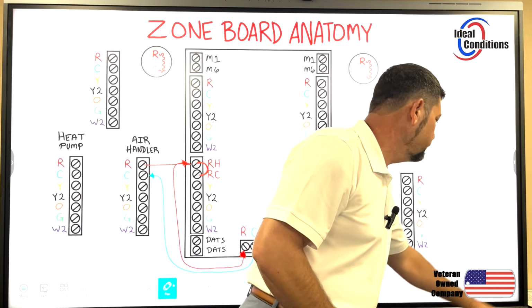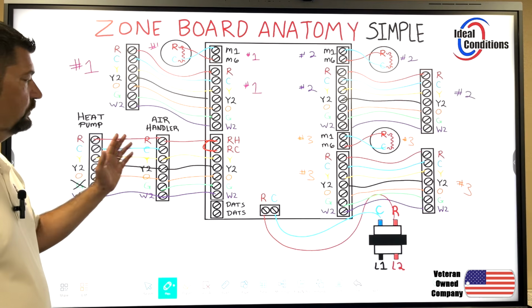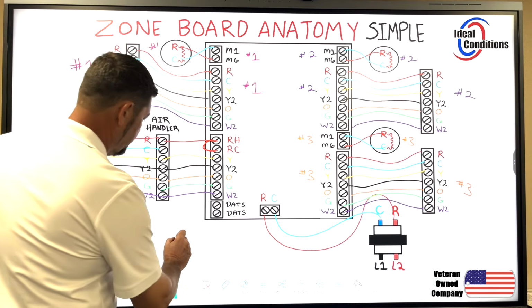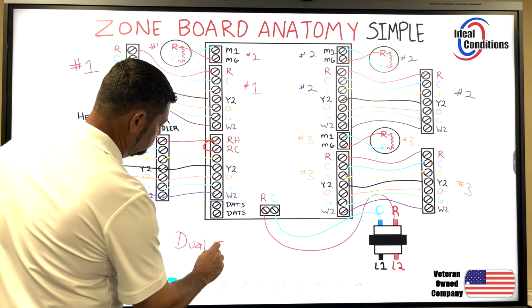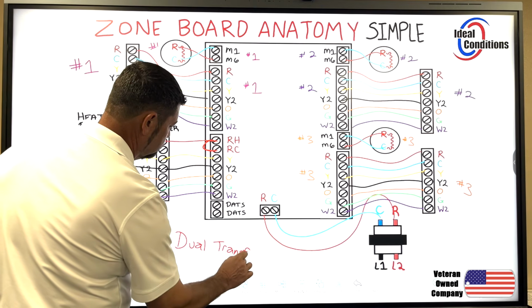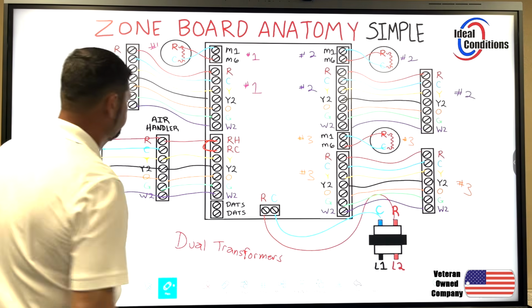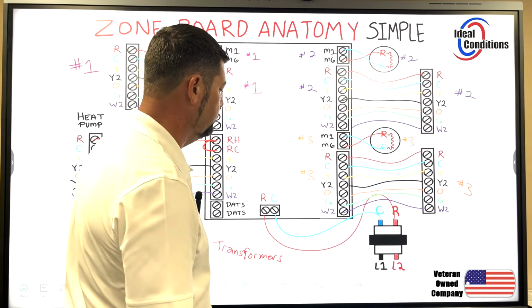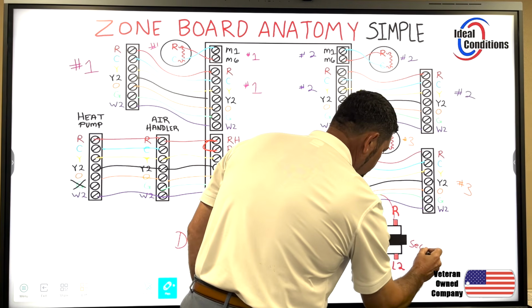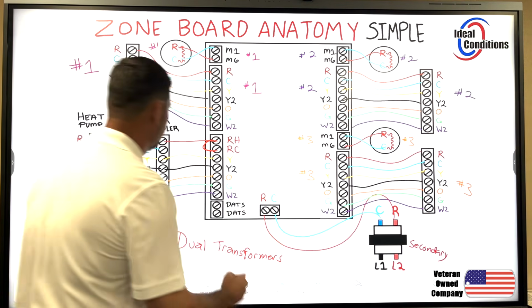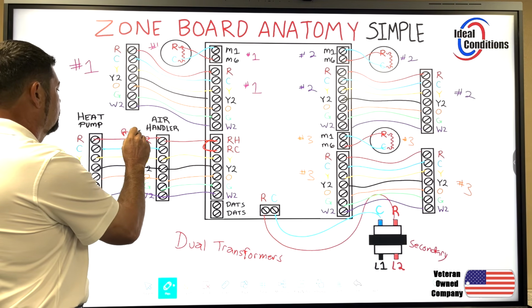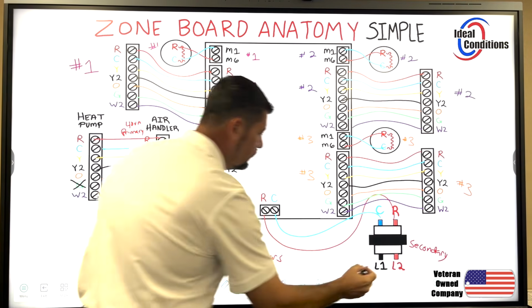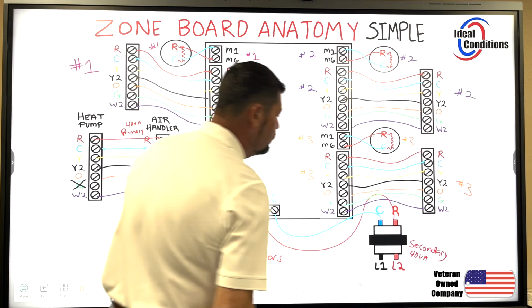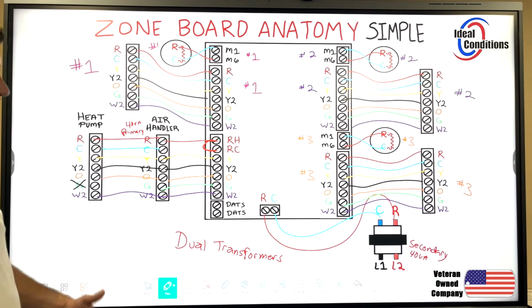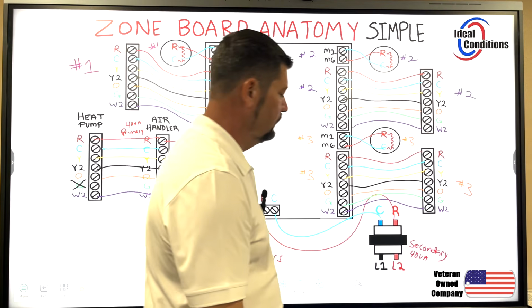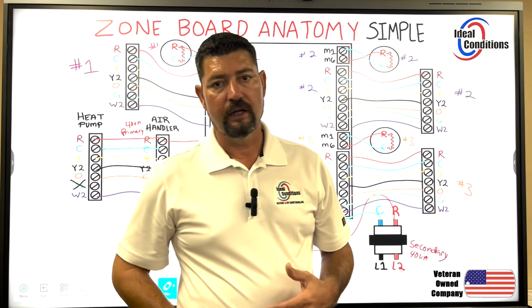I'm going to leave you off on this last page, which is dual transformers. You've got the primary in here and the secondary over here—we'll label this one secondary and this one primary, each at 40 VA, running two 40 VAs. Or you can just wire it the other way as a single transformer at 75 VA.